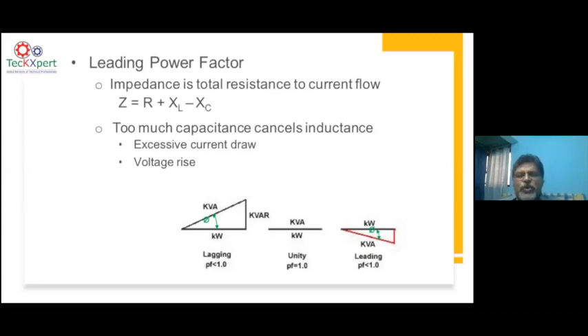When I say capacitive loads, all these loads use a capacitor at the rectifier for creating a DC voltage. So it is fundamentally a capacitive load. That means when you connect all these capacitive loads to a grid, naturally it causes a leading power factor. Many times your capacitor bank becomes useless, because there is already a leading power factor, so why would you switch on a capacitor bank there? The leading power factor problem is very common in conventional setups with this sort of load, which is substantially leading, and you unnecessarily waste a lot of money on capacitors.